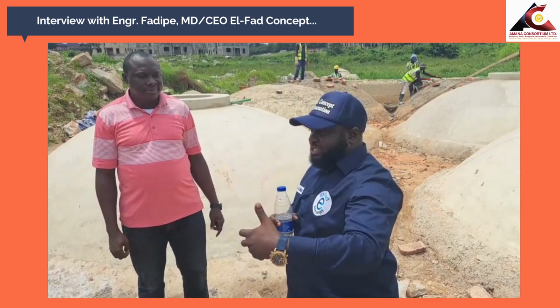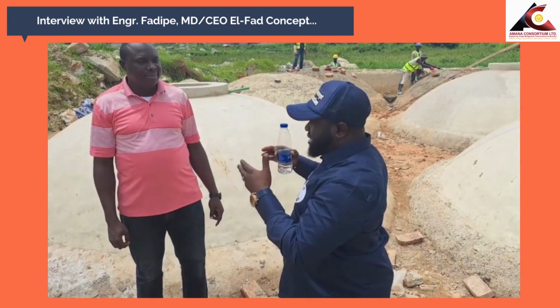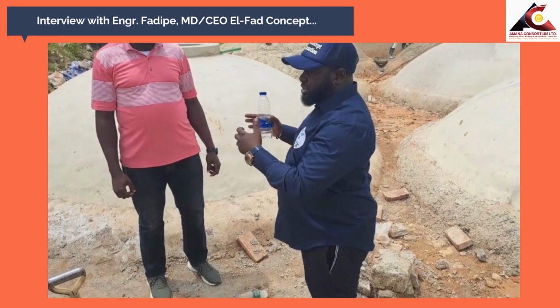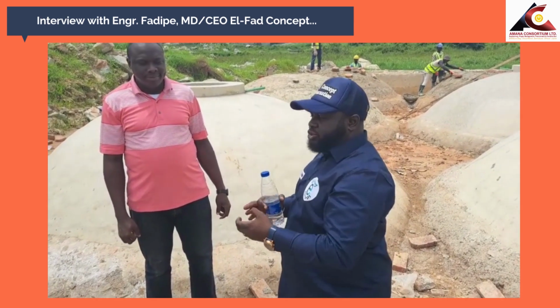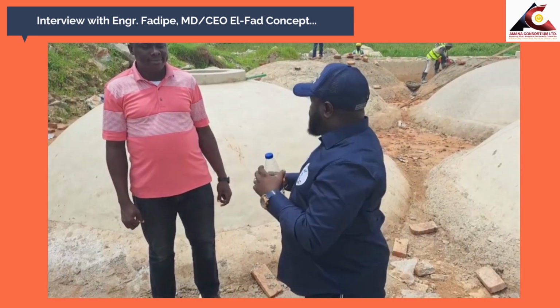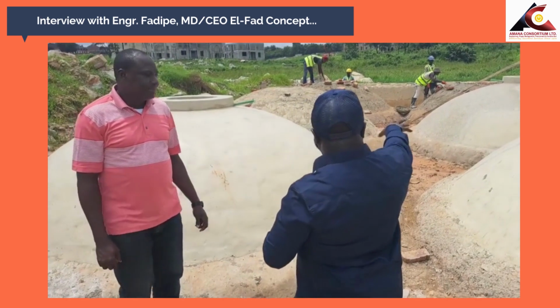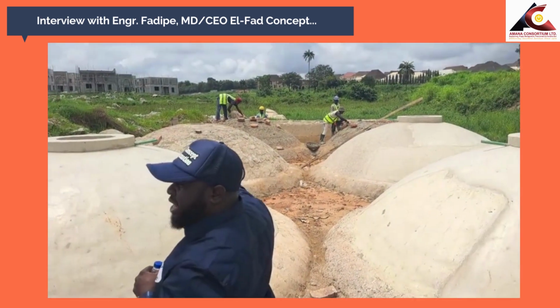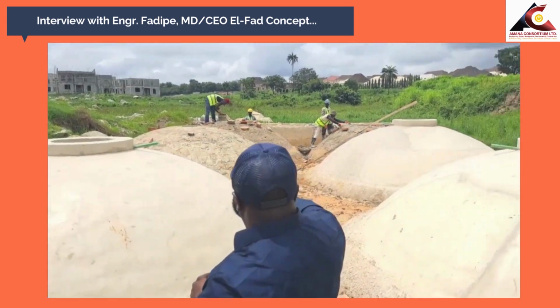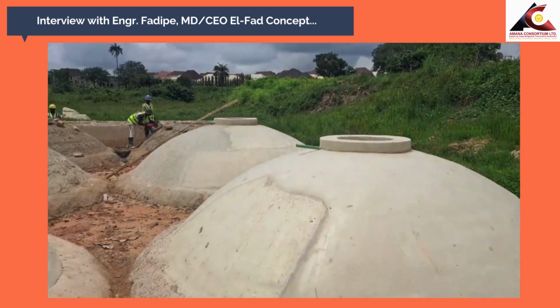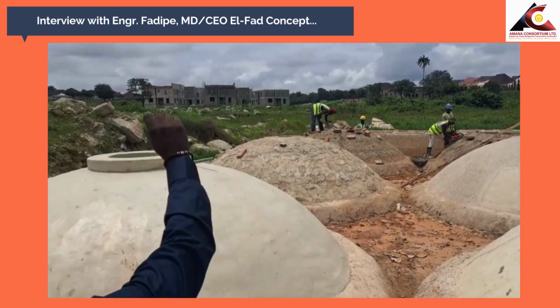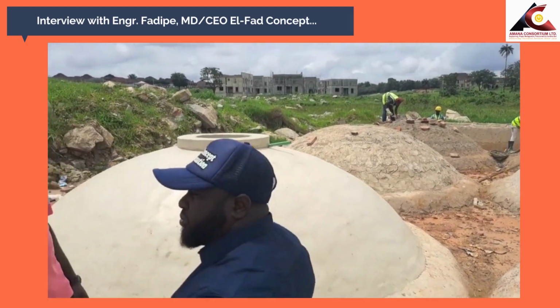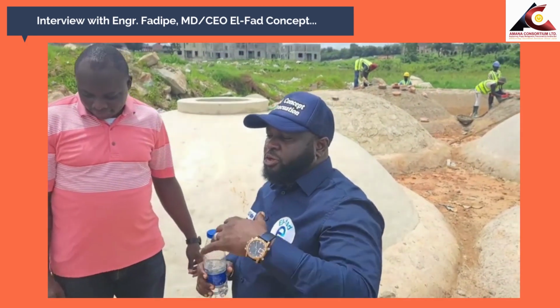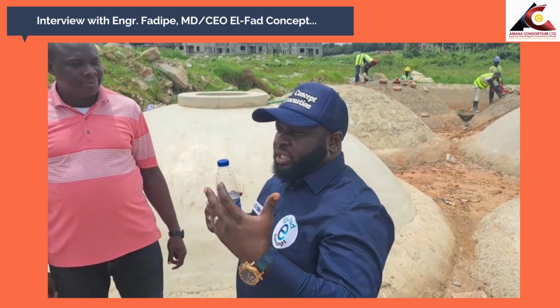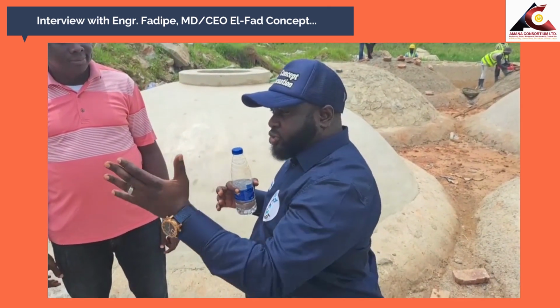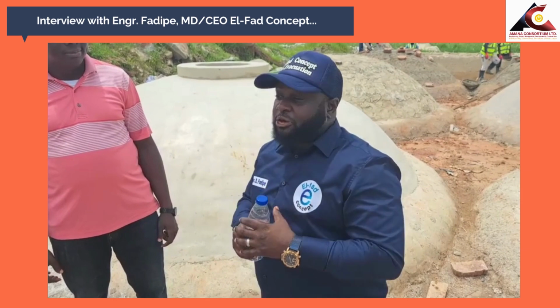Basically, your solid waste comes into the system, and within 30 days, which is the sludge retention time, SRT, bacteria will break it down into biogas and water. And of course, as it moves, what we have here is actually a 180 cubic meter anaerobic fixed dome digester. As the flow comes, it goes from one chamber to the next, and at the end it goes to the filtration bed. At the filtration bed, what we do there is to remove odor, of course, and the nutrients will just pass through the biofilters, and at the end of the day it comes out as clean water.